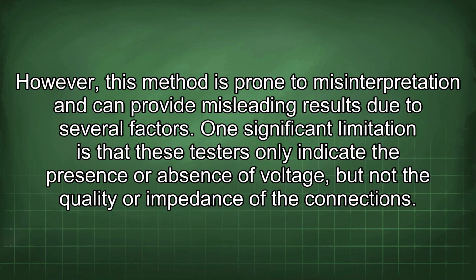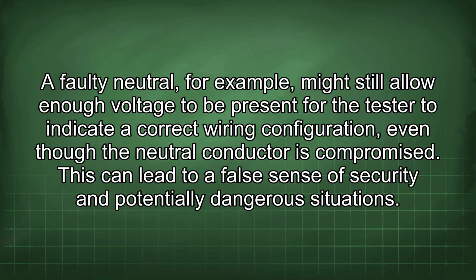However, this method is prone to misinterpretation and can provide misleading results due to several factors. One significant limitation is that these testers only indicate the presence or absence of voltage, but not the quality or impedance of the connections. A faulty neutral, for example, might still allow enough voltage to be present for the tester to indicate a correct wiring configuration, even though the neutral conductor is compromised. This can lead to a false sense of security and potentially dangerous situations.